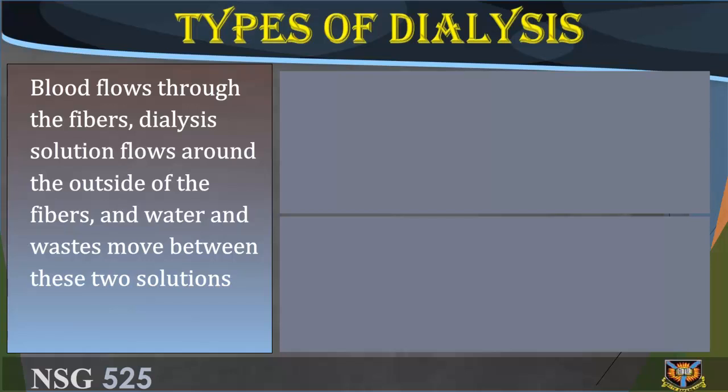The dialysis solution has levels of minerals like potassium and calcium that are similar to their natural concentration in healthy blood. For another solute, bicarbonate, the dialysis solution level is set at a slightly higher level than normal blood, to encourage diffusion of bicarbonate into the blood, to act as a pH buffer to neutralize the metabolic acidosis that is often present in these patients.